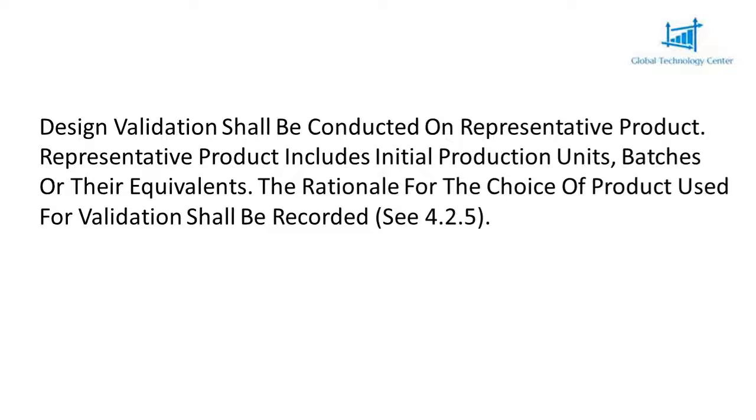Design validation shall be conducted on representative product. Representative product includes initial production units, batches or their equivalents. The rationale for the choice of product used for validation shall be recorded.